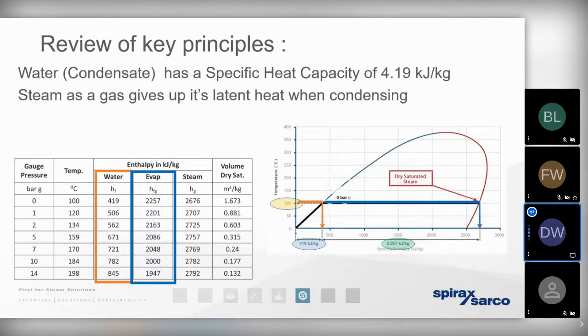But it's important to bear in mind that when that steam reaches a heat exchanger, it condenses. It gives up its heat energy. It changes state from a gas to liquid. But it's only that enthalpy of evaporation, that latent heat, the energy shown in the box in blue, that is transferred across into the process. So that means that liquid condensate, that byproduct of heat exchange, is exactly the same as the amount of energy that we added to the water to bring it up to boiling point.